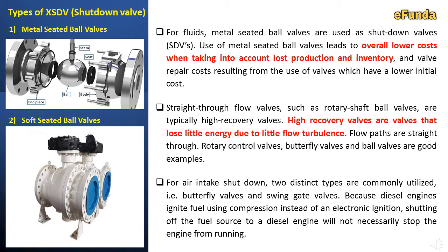Straight through valves such as rotary shaft ball valves are typically high recovery valves. High recovery valves are valves that lose little energy due to little flow turbulence. The flow paths are straight through. Rotary control valves, butterfly valves and ball valves are good examples of high recovery valves.